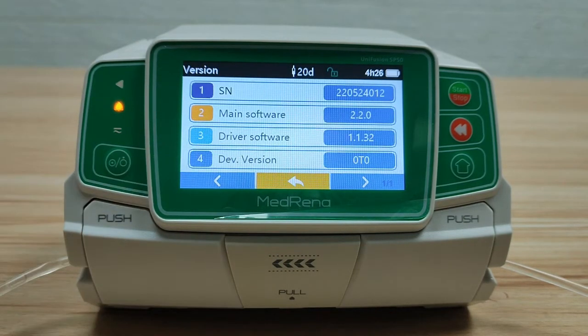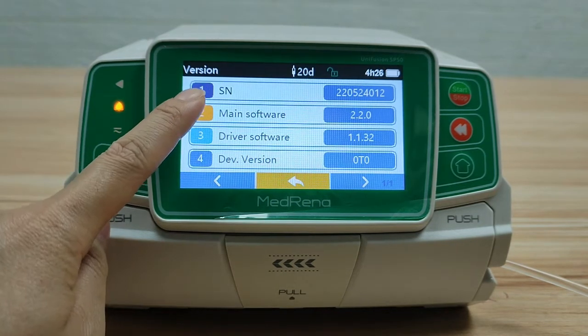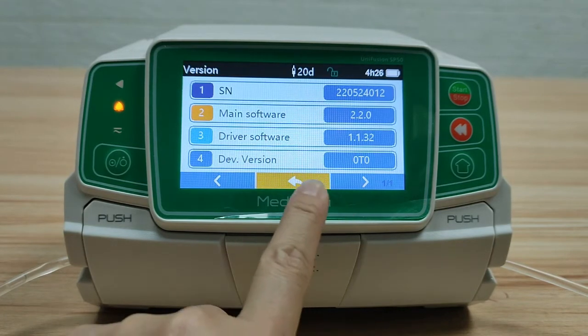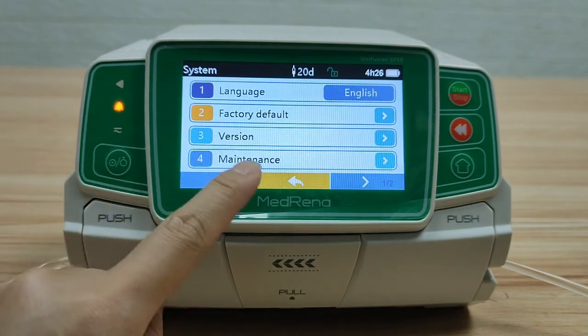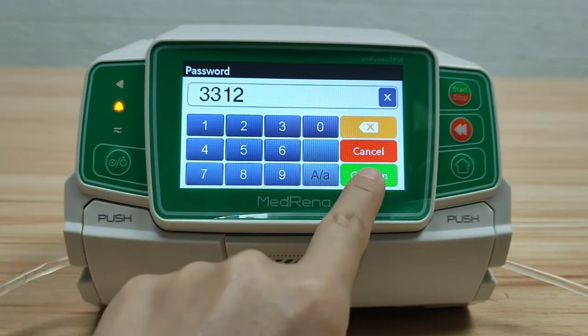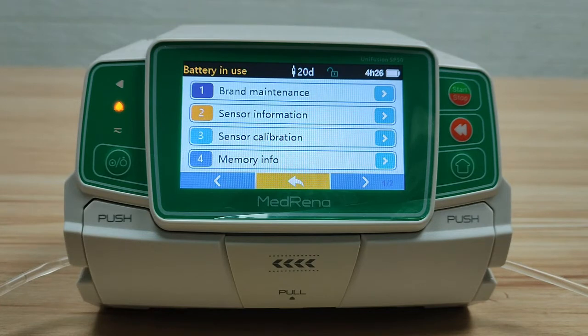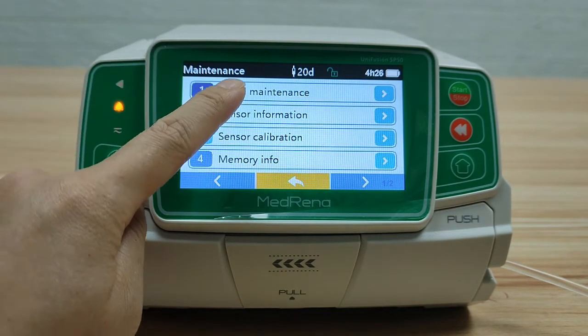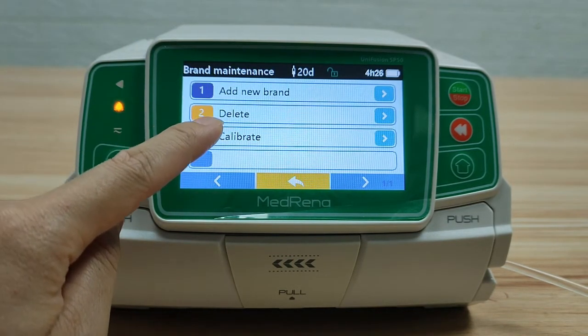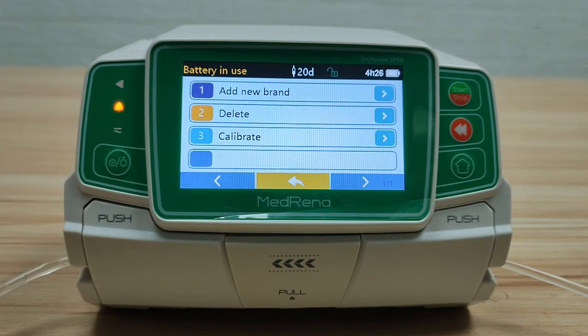Version: here it shows the serial number, the software version, and the device version of the pump. Maintenance: enter the password. There are different settings under this item. First, brand maintenance — we can add, delete, and calibrate the infusion set brand. We will explain how to add a new infusion set brand and calibrate it in the next video.